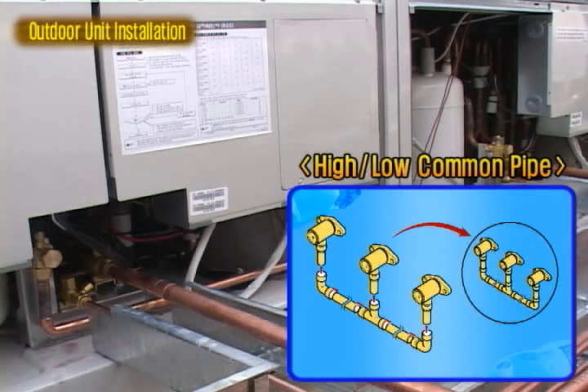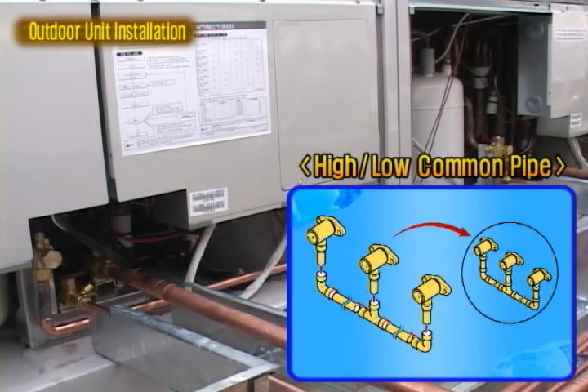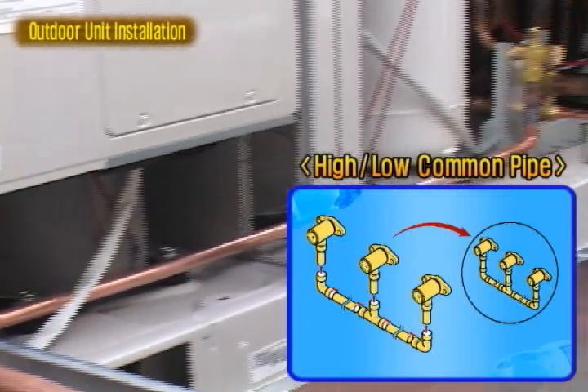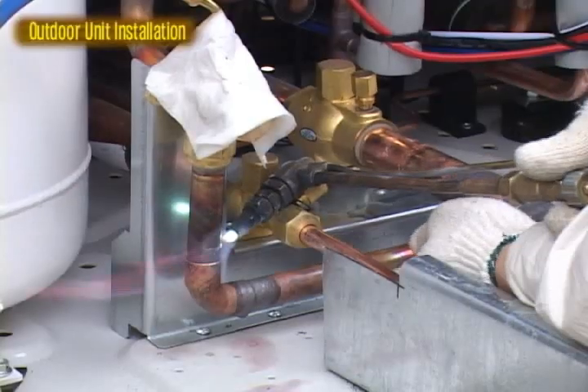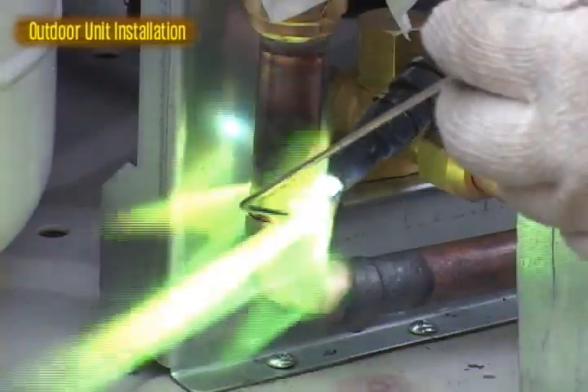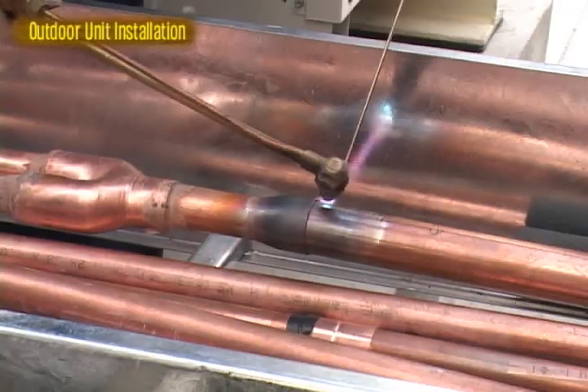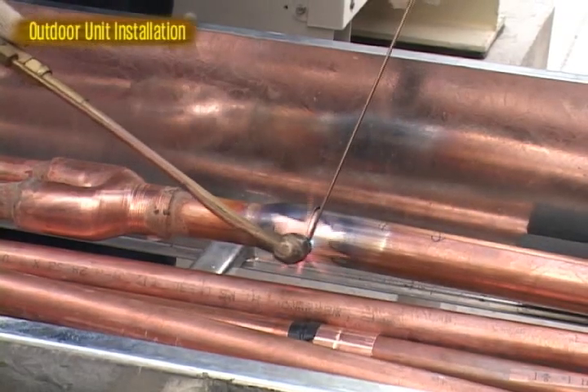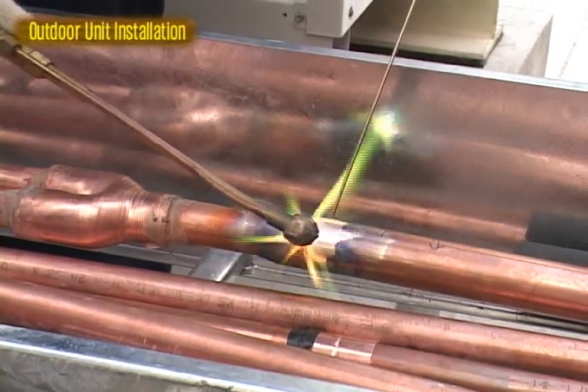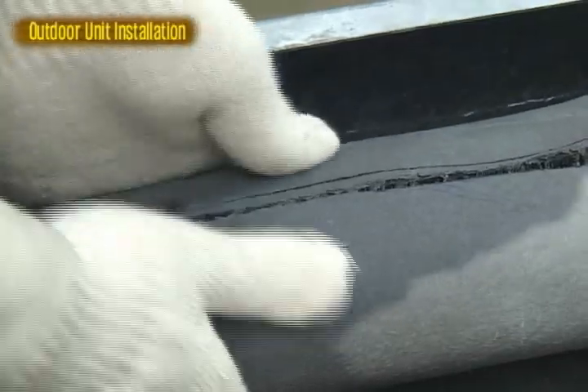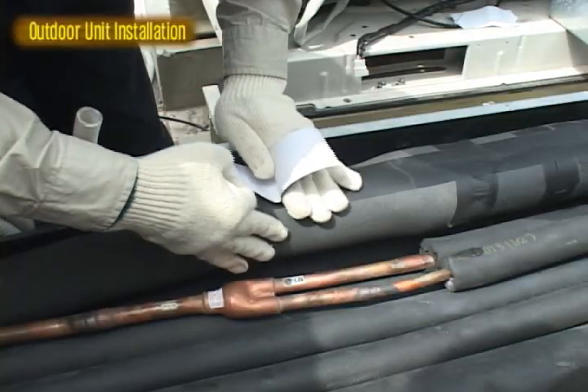For installation with more than 2 outdoor units, arrange common high and low pressure pipes in order to maintain balance between the units. Branch pipe is connected between the outdoor units and connected again to indoor units. Cover high and low pressure refrigerant pipe with insulation to avoid dew.